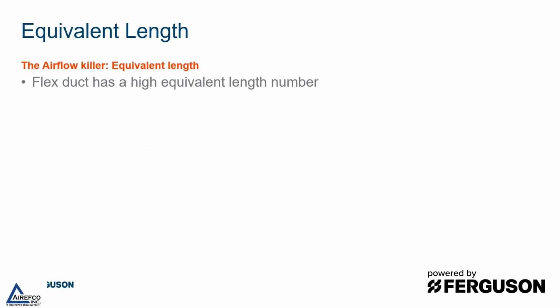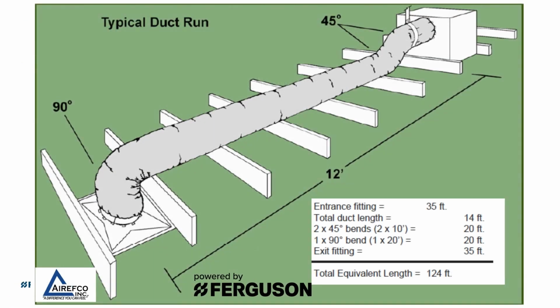One term that you should be familiar with when running ductwork is equivalent length. Equivalent length is an airflow killer, and flex duct has a high equivalent length number. Here we have an example of equivalent length. We have a flex duct run that is 12 feet from the unit to the register, but we have fittings in the run: two 45-degree elbows that have an equivalent length of 20 feet, one 90-degree elbow that has an equivalent length of 20 feet, and an exit fitting that has an equivalent length of 35 feet. Adding all the fittings together, we have a duct run equivalent length of 124 feet.